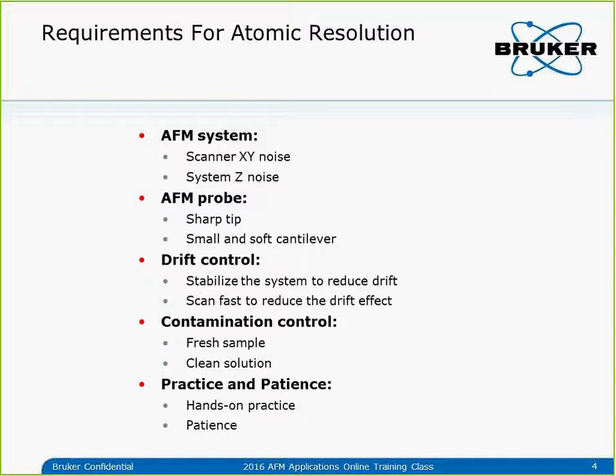Next is the AFM probe — that's an important factor. We need to use a sharp probe because we are imaging the atomic lattice. A sharp probe is not that critical for contact mode probably, but it's very critical for peak force tapping mode because we want to image those lattice sites one by one, not many together. For probe size, a small and soft cantilever is important. The small cantilever has better deflection sensitivity — it's more sensitive — and a soft cantilever can control the force better.